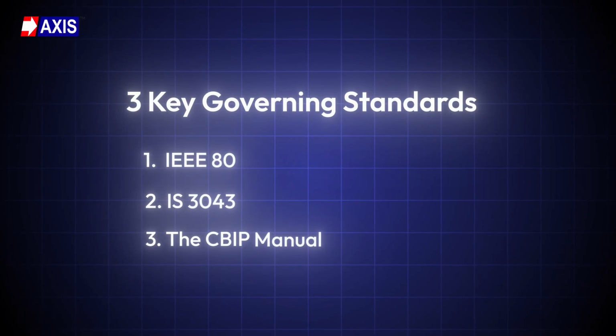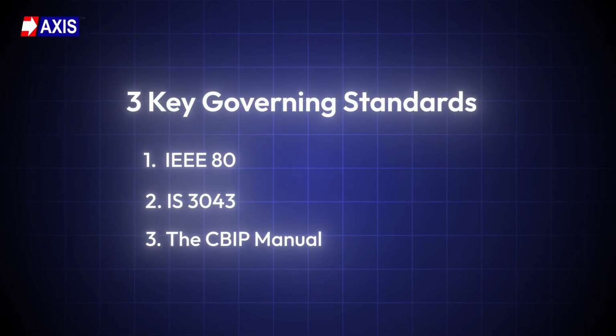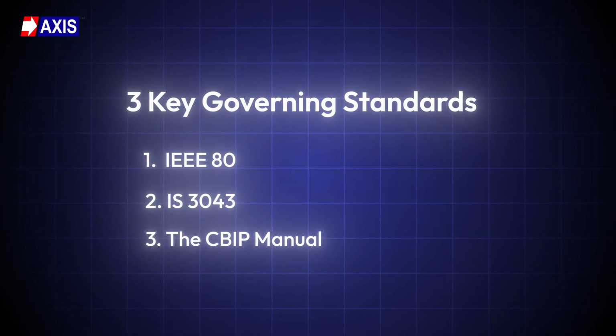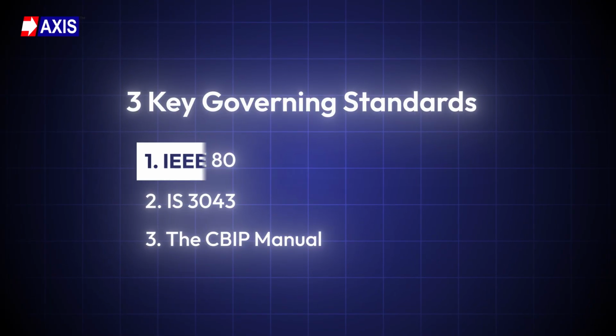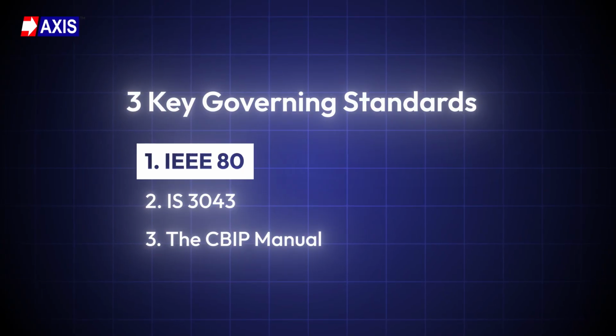Lastly, do you know where these tests, formulae, and procedures actually come from? They come from 3 key standards that govern everything that we have discussed in this video so far. First of all, IEEE 80 is the primary international standard for substation earthing design. It establishes safe limits for touch and step voltages, provides a structured design procedure, and defines the analytical methods used for GPR and grid impedance calculations.